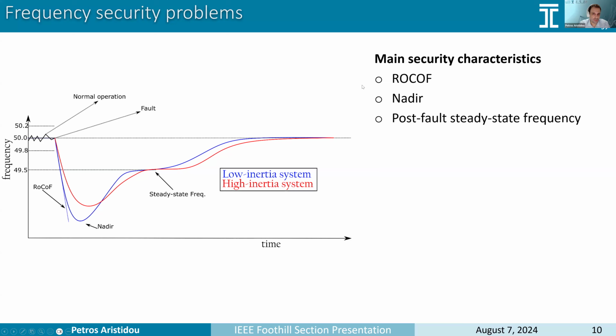The main security characteristics for this frequency response are the RoCoF. So we want the initial rate of change of frequency to be limited. Otherwise, it's going to impact the different protection schemes that we might have. It might trigger anti-islanding protections. It might create problems to synchronous generators that might be connected. We need to limit the nadir, so the dip where the frequency ends up, because otherwise we might have unwanted disconnection of devices, or activating under frequency load shedding schemes, and of course the post-fault steady state frequency needs to be within a certain bound.